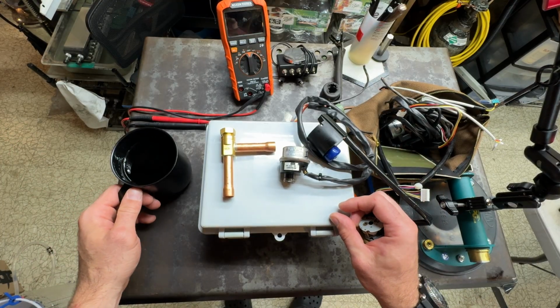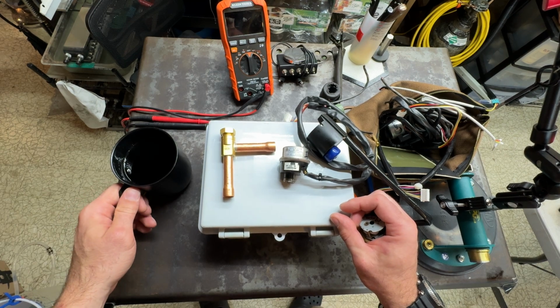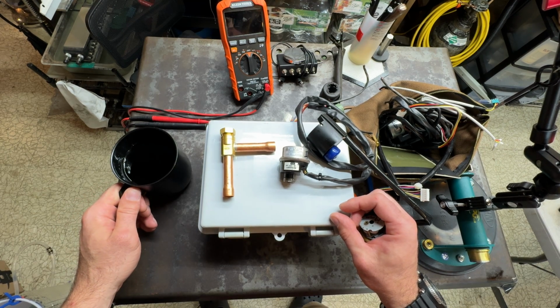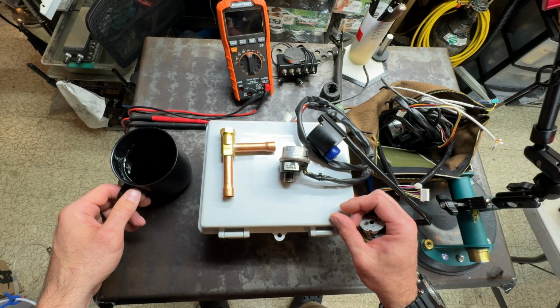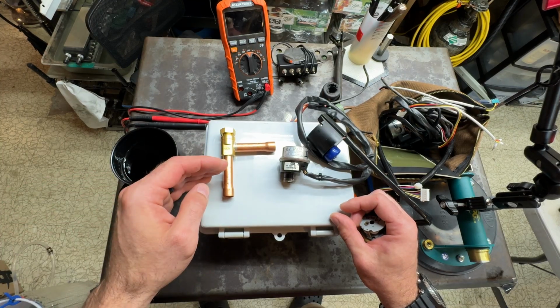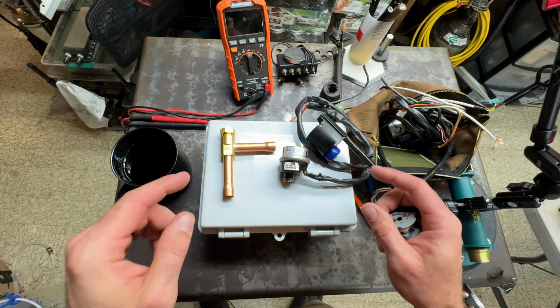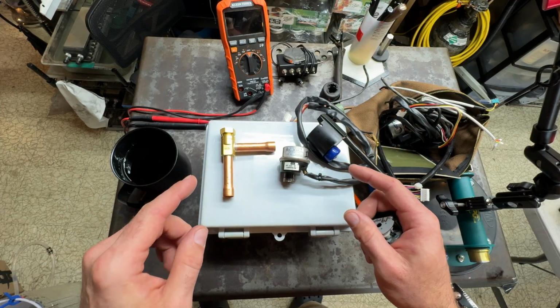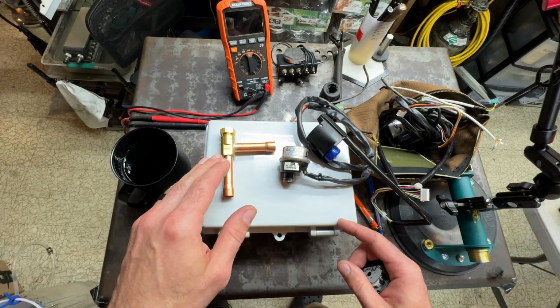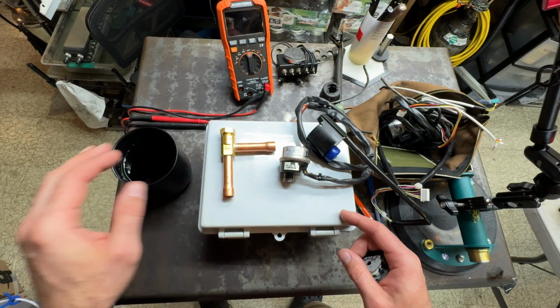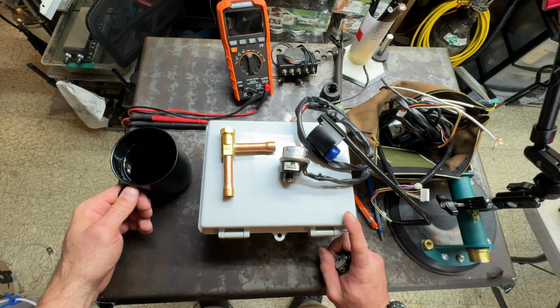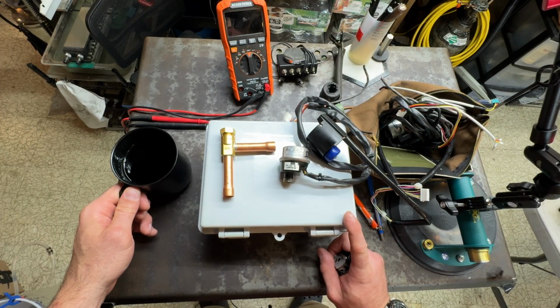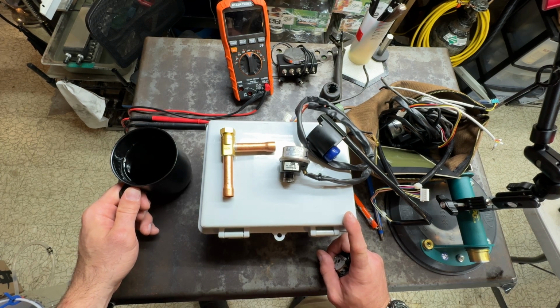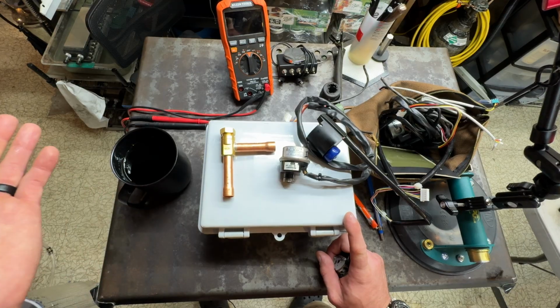Now with Daikin, you've got to always do this in cooling, don't do it in heat mode, different things are going on that can really get confusing. Always cooling, wide open cooling. You shut this down and watch your sensors, your pipe in and pipe out sensors. If this is truly shut, those two measurements are going to start to equalize, and normal error might be like a degree or maybe two. These sensors sort of degrade over time, or some of them completely fail.